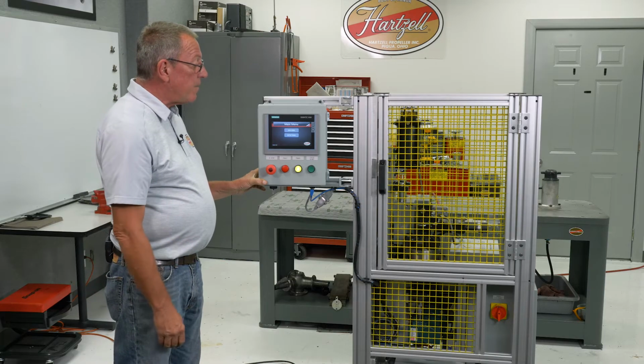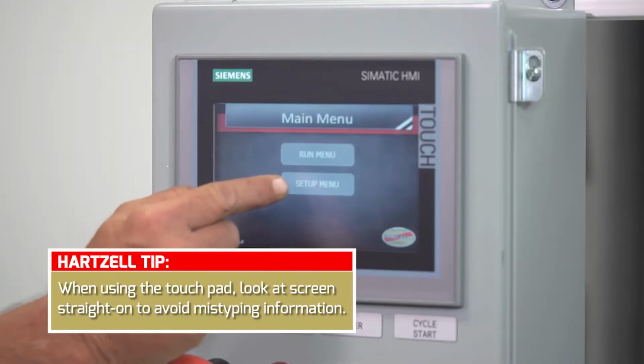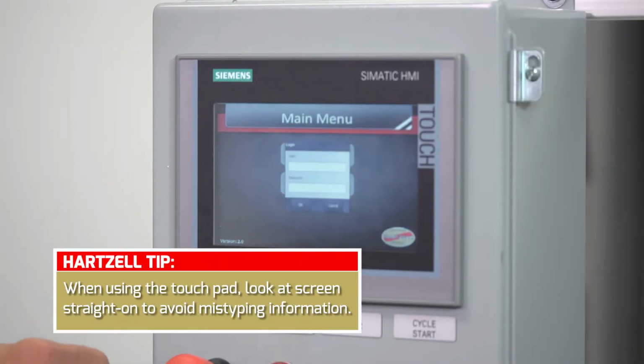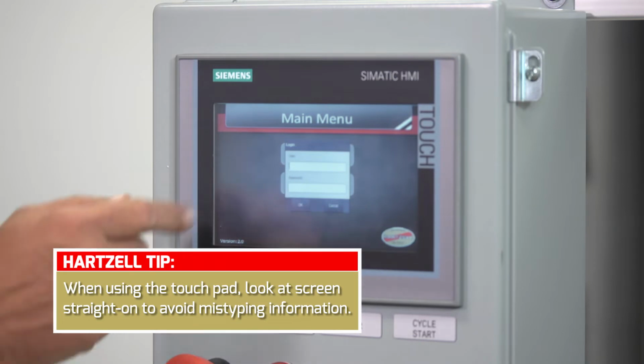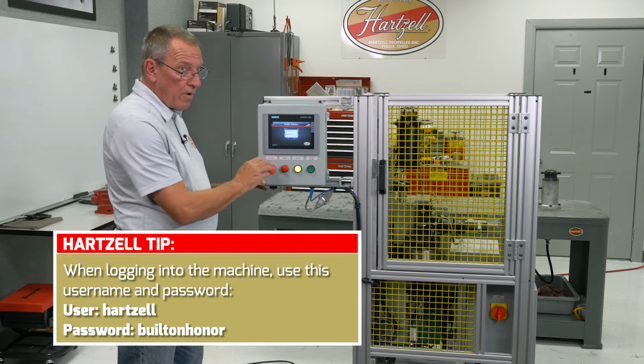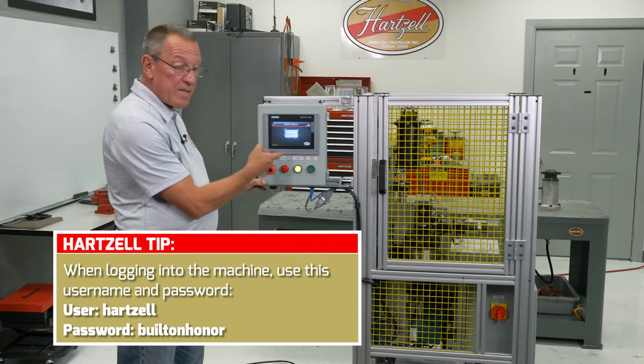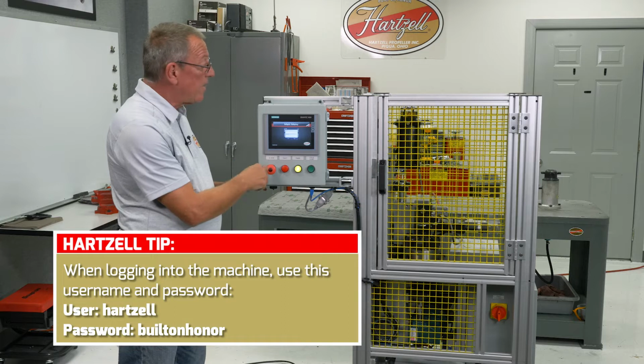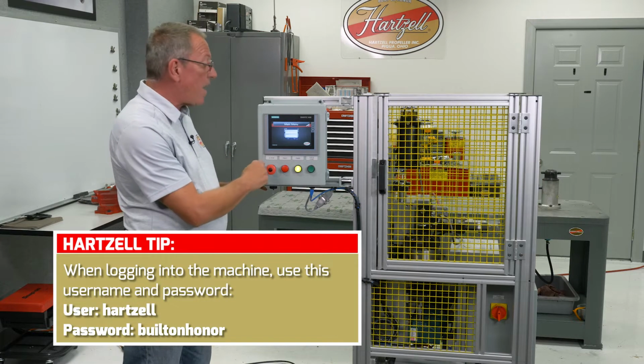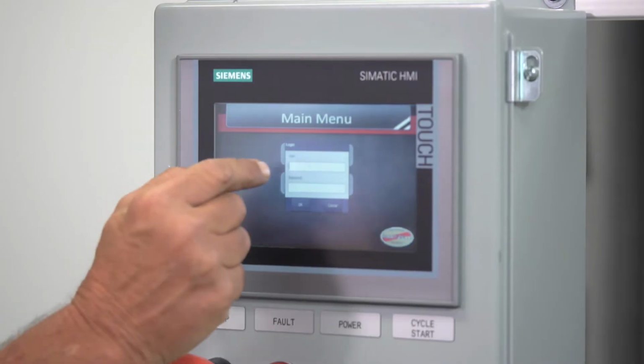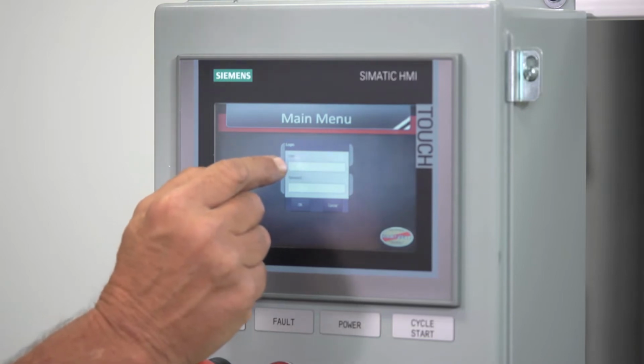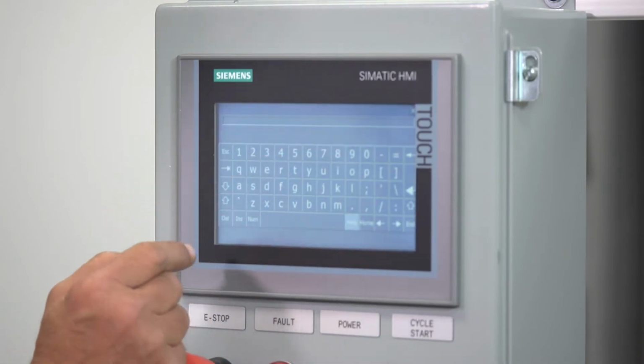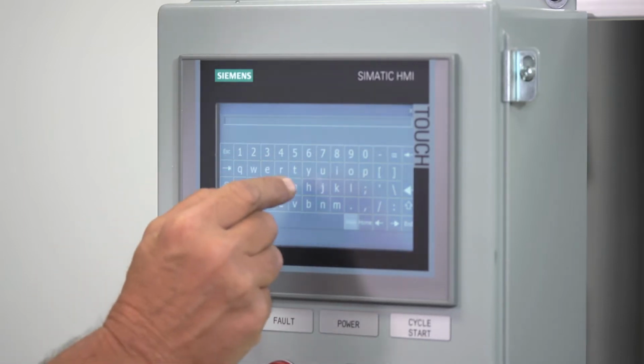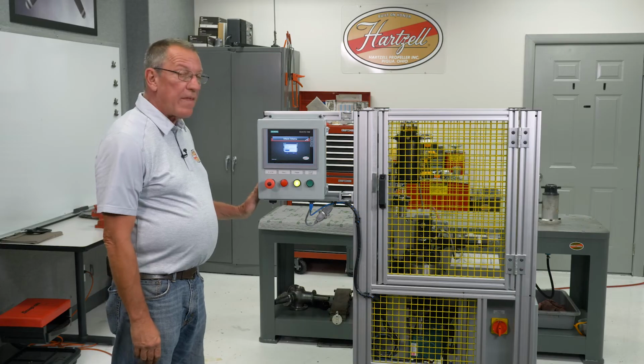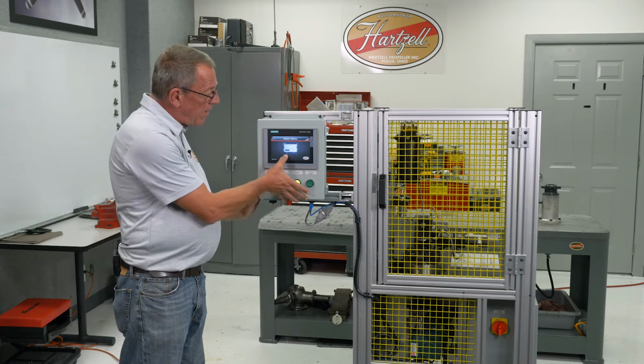Since we're going to be calibrating the machine, we're going to run the setup menu, and that brings up a login screen. So you need to put in the user and the password. The user is in the manual, as is the password, but the user is Hartzell, and the password is built on honor. So we'll hit on the user bar here. That brings up this keypad. We'll type in Hartzell. So now that I've entered the user and the password, I'll press OK.